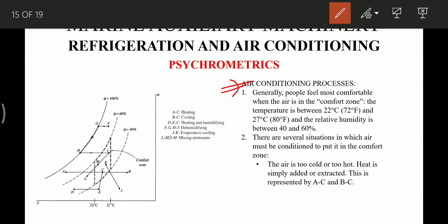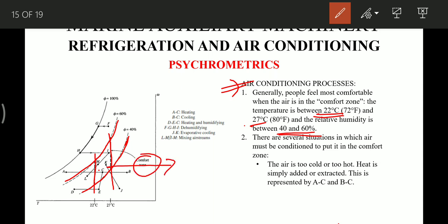Now let's see how these processes take place in the air conditioning plant. People feel most comfortable when air is in the comfort zone — that is when the temperature is between 22°C to 27°C and relative humidity is between 40% to 60%. On the psychrometric chart, this is bounded by the 40% and 60% relative humidity lines and the 22°C and 27°C temperature lines. The area inside these bounds is known as the comfort zone.